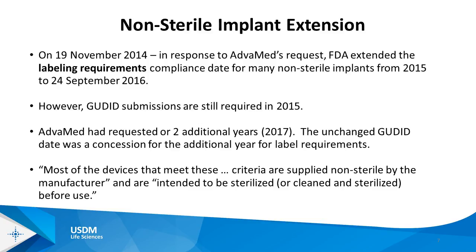Very important to note that the submission of data to the Global Unique Device Identification Database, or the GUDID, is not extended. So it only applies to the label requirement. So the placement of the UDI on the label and the date formatting requirement are extended to 2016, but the data requirements still exist for 2015.